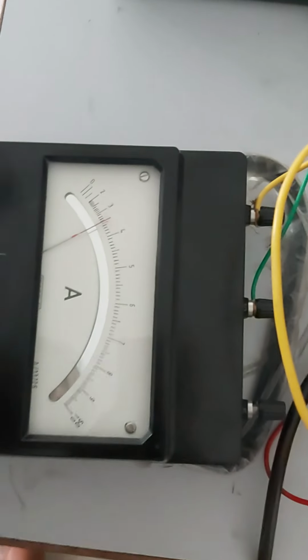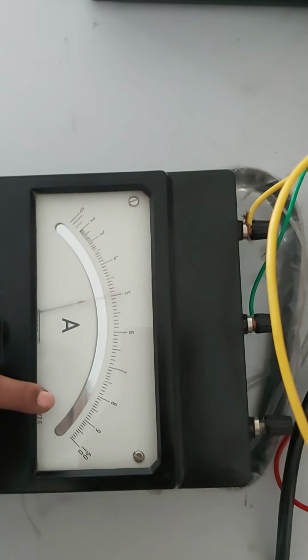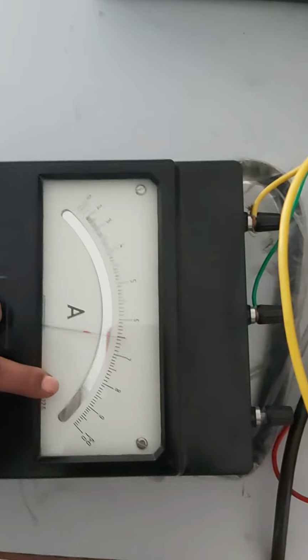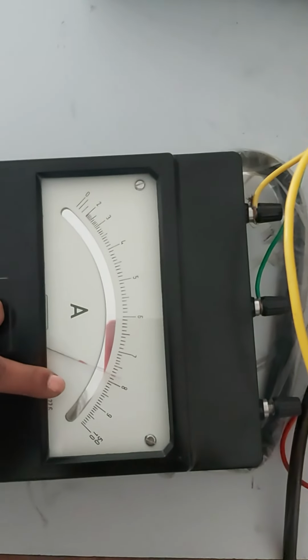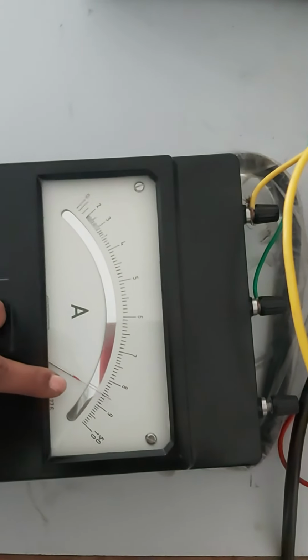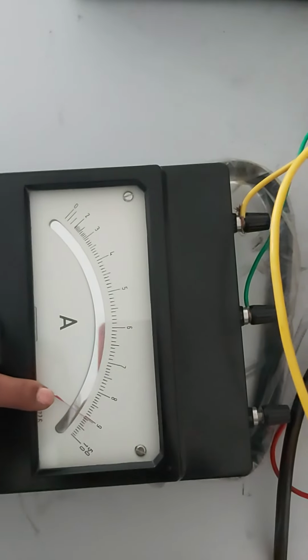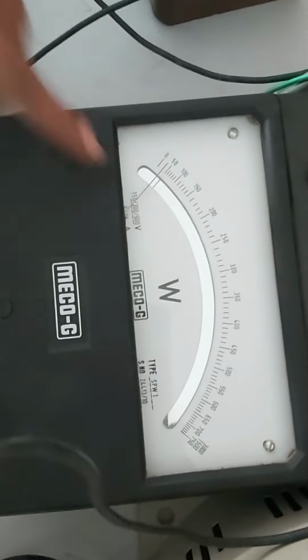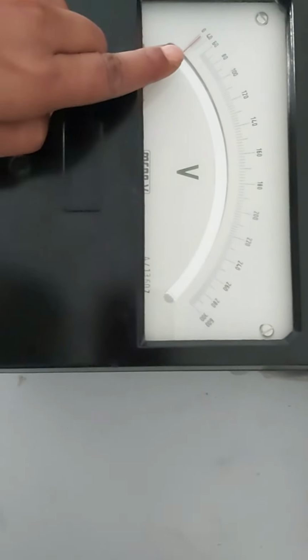Now we have to perform the short circuit test on this secondary side. Slowly vary the variac up to the rated current flowing through the ammeter. The rated current of the transformer is 9 amperes, so you have to apply 9 amperes on the transformer. You can observe the wattmeter shows 50 watts and the voltmeter shows 20 volts.